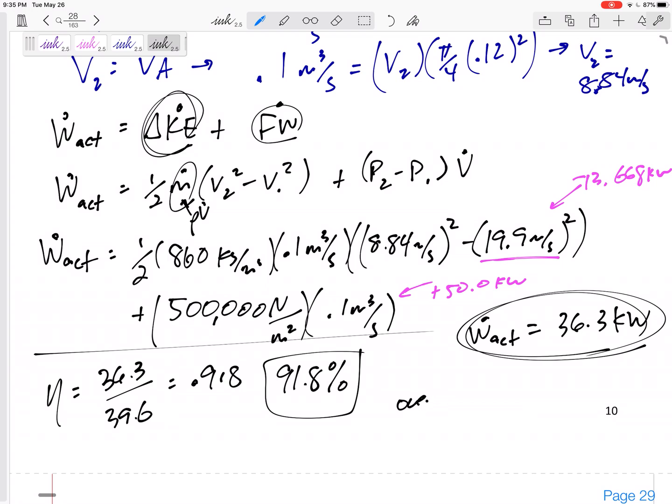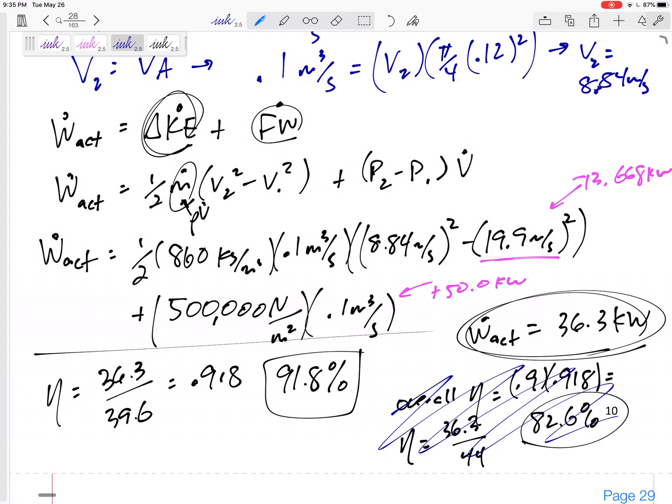Now this one didn't ask for it, but the overall efficiency would be the efficiency of the motor times the efficiency of the pump would be 82.6%. Another way to find this overall efficiency would be 36.3 over the complete 44, which would be also the 82.6%. All right. The question didn't ask for that. So let's don't get into a habit of answering things that it doesn't ask for. But many times it might ask for the overall efficiency of the pump.